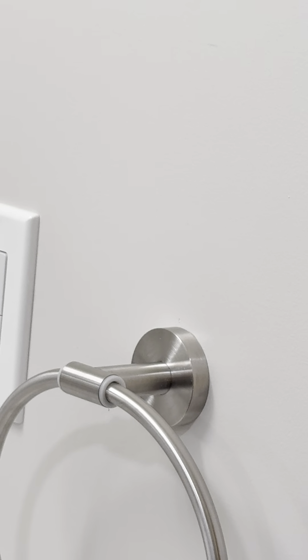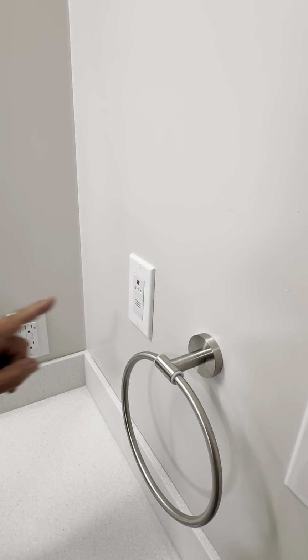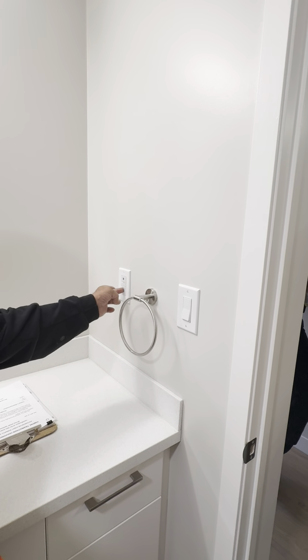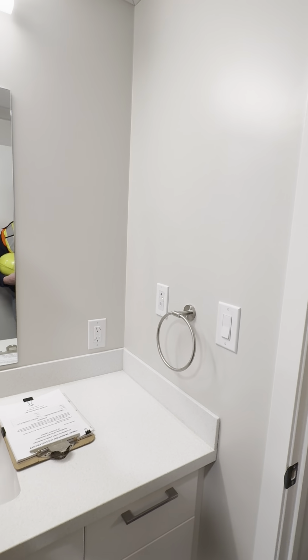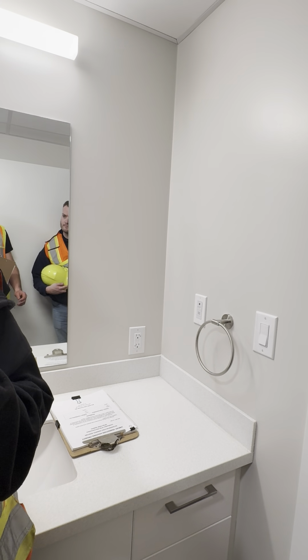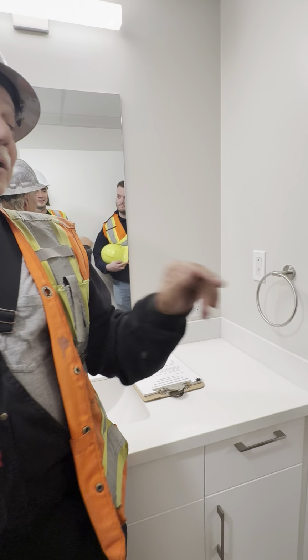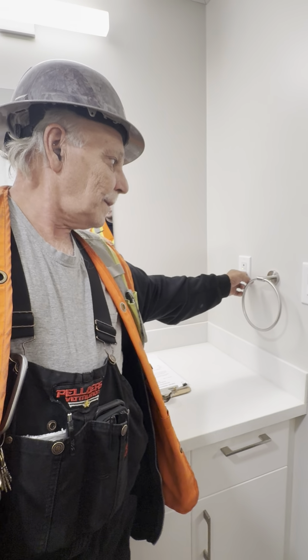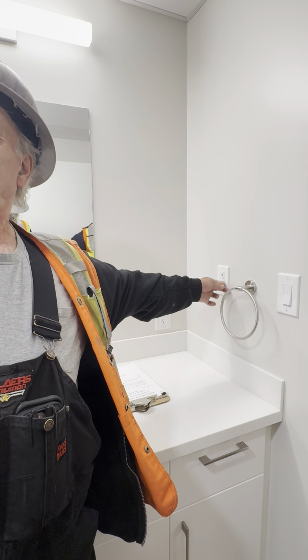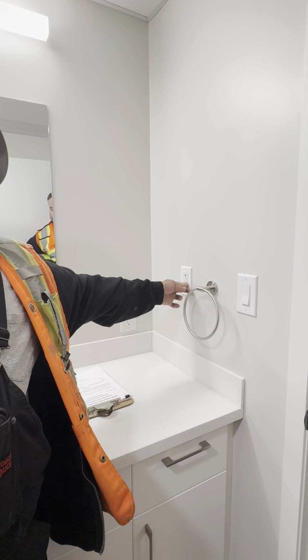Now, if somebody complains that the button has been held for a certain length of time, you're going to see that all of a sudden it starts to flash. That first one means the button is locked. You can hit this, do whatever you want, it's never going to turn on. I have had numerous calls for HRVs that don't work on the bathroom control, because it's something like a 5 to 10 second hold. Somebody held it for 5 seconds and locked it in off, so it'll never turn on.